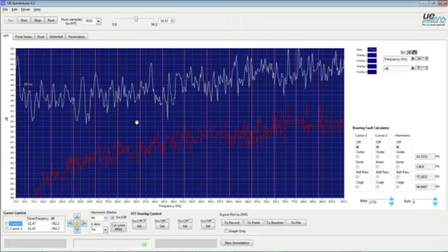With a normal nuisance corona event, the highest stress on the electrical sine wave is on the negative half cycle, and that occurs on a very predictable, repeatable, known time base of every 16 milliseconds. So that being very consistent, uniform, and repeatable on the frequency analyzer at least, you get a nice display of uniform, consistent 60 Hz harmonic peaks.